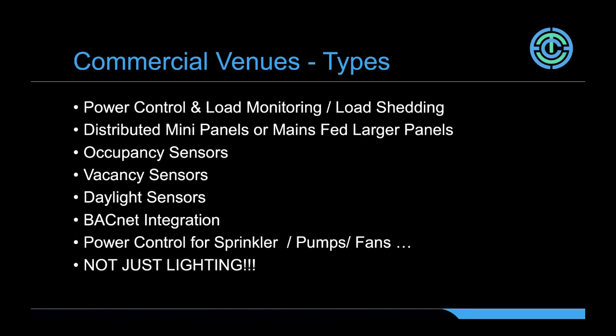The systems that we have, all of our systems, Foundry, Sensor, Echo, even Echo Flex, have demand response dedicated inputs at the panels, and the control systems have the ability to do load shedding through the intelligence of the program environment and user interfaces. So load shedding is something that will be becoming a requirement here in Ontario and Quebec very, very soon. The systems that you're going to be putting in today or retrofitting tomorrow, we're going to want to make sure that they're able to do that.